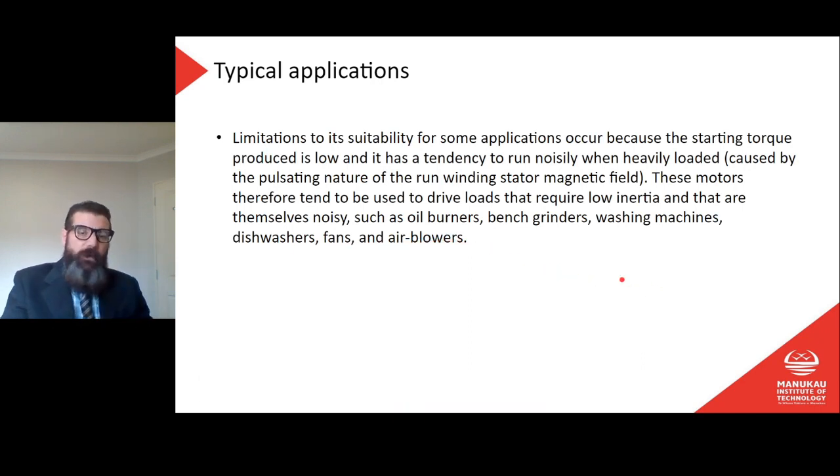Limitations occur because the starting torque produced is low, and the motor has a tendency to run noisily when heavily loaded, caused by the pulsating nature of the run winding stator magnetic field. These motors therefore tend to be used for drive loads that require low inertia and are themselves noisy — such as oil burners, bench grinders, washing machines, dishwashers, fans, and air-blowers.